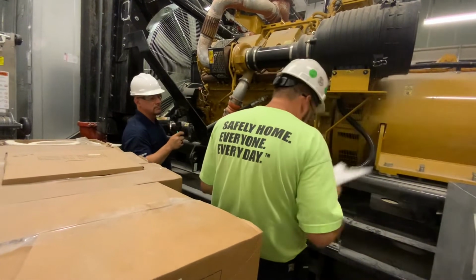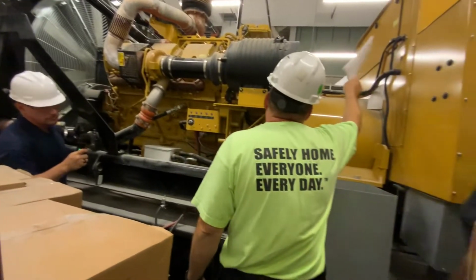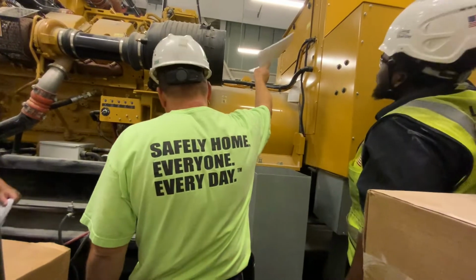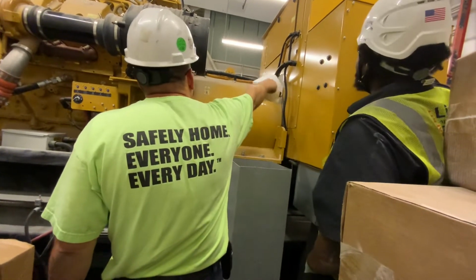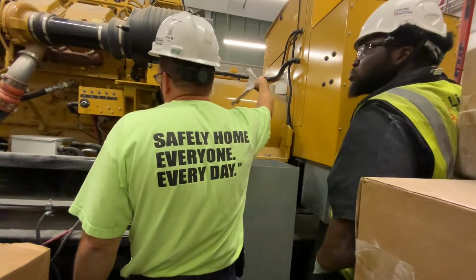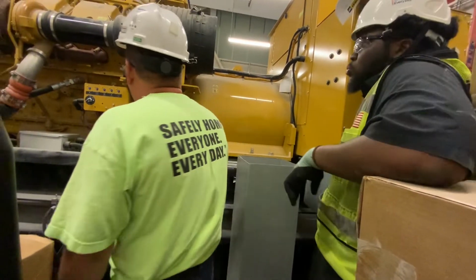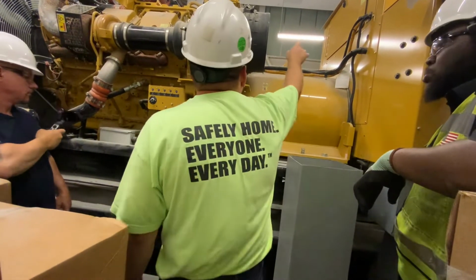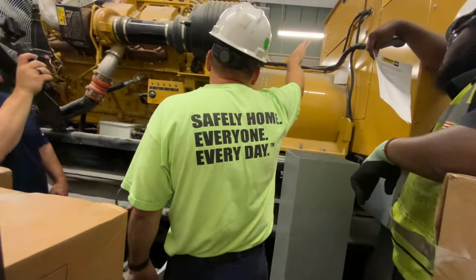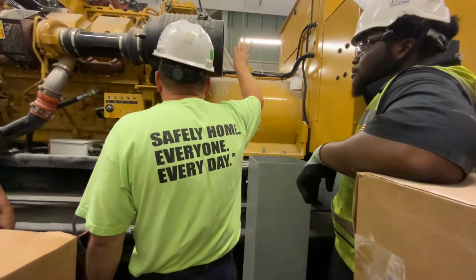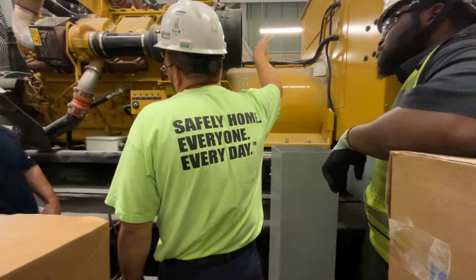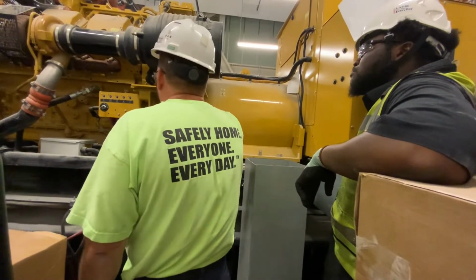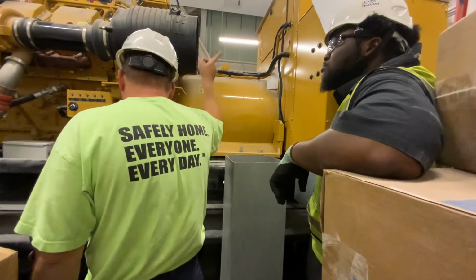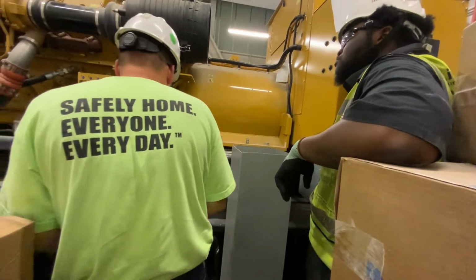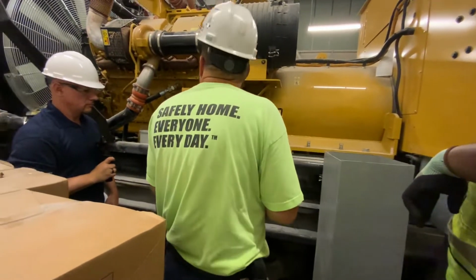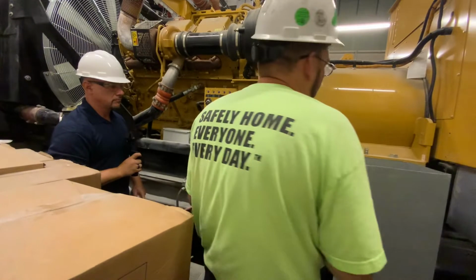And then up in the back here, we're not really going to be able to open that panel, but up in there, there's a few circuit breakers. One's for an alternator strip heater, which basically keeps the windings warm all the time, keeps condensation out of there. And then your jacket water heater also has a double pole breaker that operates out of there. So this is being fed from the building, and it's typically a 208 60 amp feed to it, and then it has two sub breakers inside of our panel there. So if you have an issue with just one device not being hot, that's where I would check first, up in that panel, make sure something didn't trip. And that's pretty much it on this side. We'll walk around to the other side and check that out.